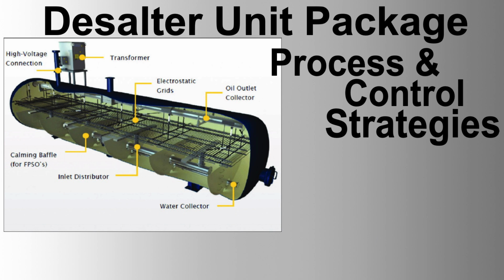2. Emergency shutdown. If a high-level, high-pressure, or low-voltage condition is detected, the system will automatically shut down, closing all inlet and outlet valves and deactivating the electrostatic field. Address the cause of the shutdown before restarting the system.